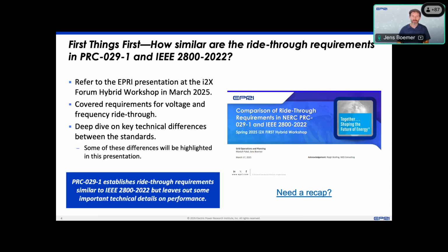But first things first, the question of course is how similar are the ride-through requirements in PRC 29 and IEEE 2800, because only if they are similar enough does it even make sense to consider using IEEE 2800.2 as a support for compliance with PRC 29. So this was presented back in March last year by my former colleague Manish Patel at the i2X workshop, and covered the voltage and frequency ride-through in good technical detail. It also highlighted some of the differences between the standards, and we'll mention some of this today too. But overall, PRC 29 establishes ride-through requirements that are quite similar to IEEE 2800.